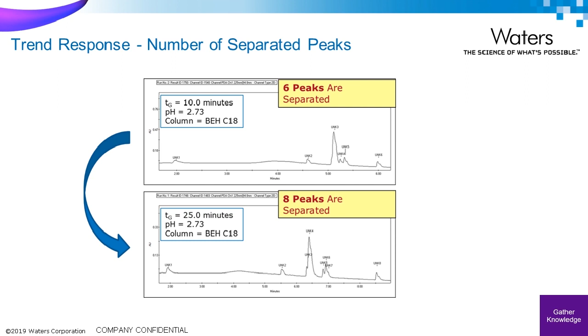An example of a trend response that we would use to measure the quality of the separated peaks would be the number of separated peaks. So in this example, we show 2 chromatograms from a BEH C18 column at 2 different gradient times, both at pH 2.7. And in the top chromatogram, you see 6 peaks separated, and the bottom you see 8. So you can see that just moving to a longer gradient in this case would improve the separation slightly.